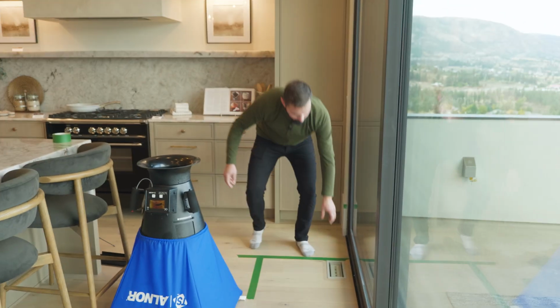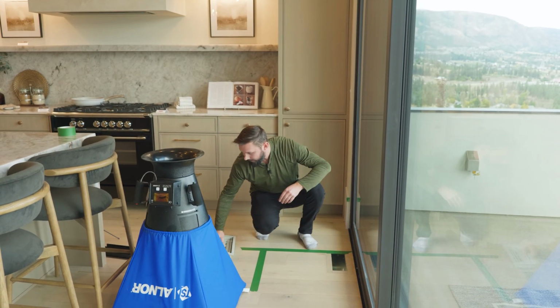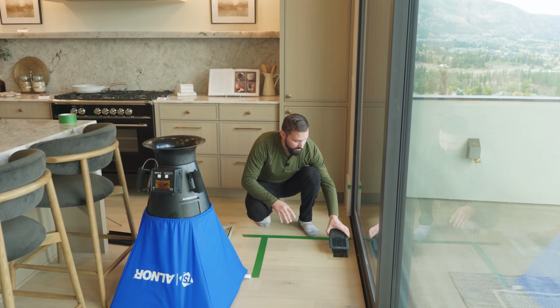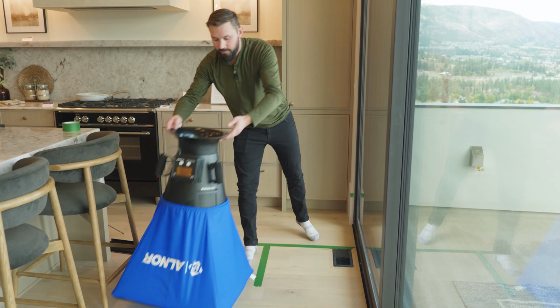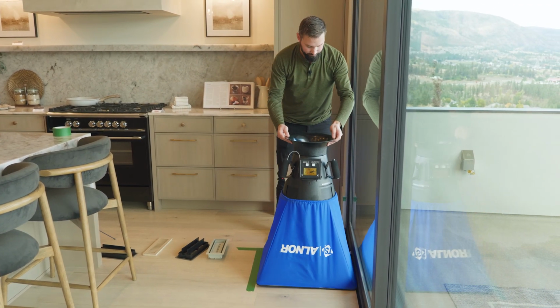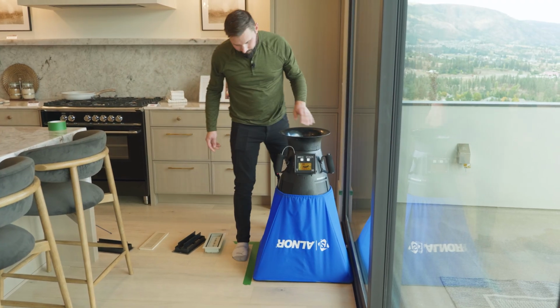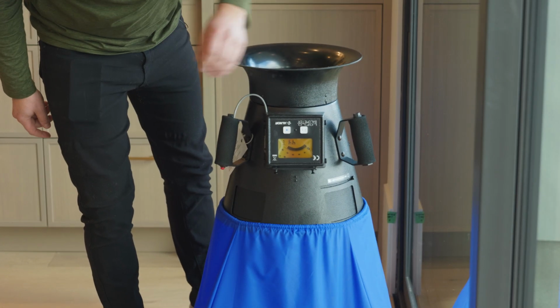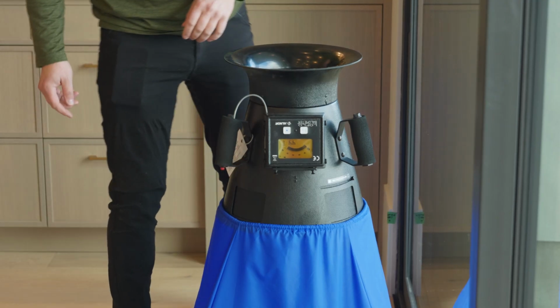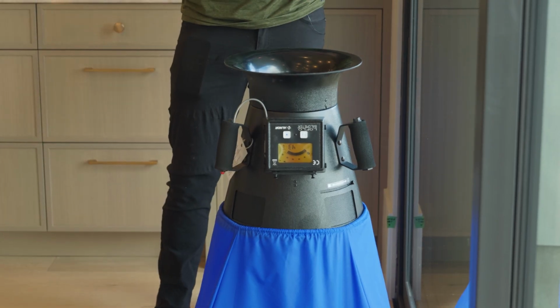34 CFM coming out of there right now. Whereas if we were planning on our system delivering 40 plus CFM of air in order to keep everybody comfortable, then we're going to have to change some system settings and use a lot more energy. You can see here that if I was commissioning this system using these vents, I'd be getting 44 CFM of air out of there. And that's a big difference. That's a 30% increase in airflow coming out of this vent compared to another with the exact same furnace settings.